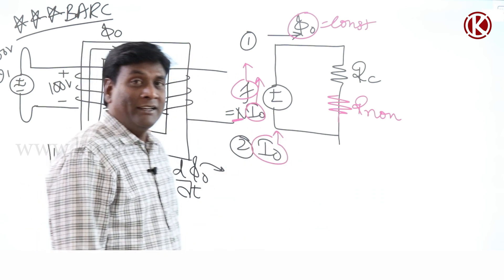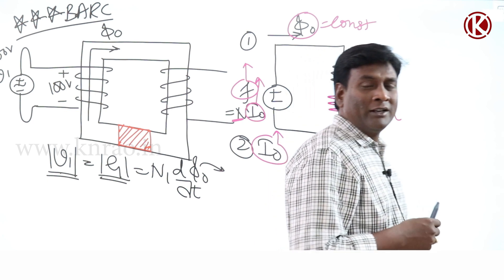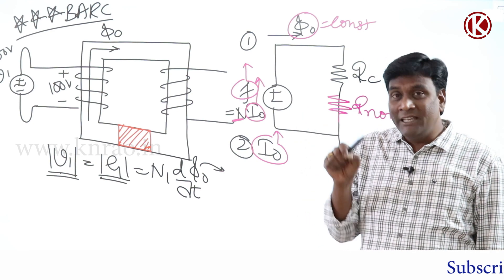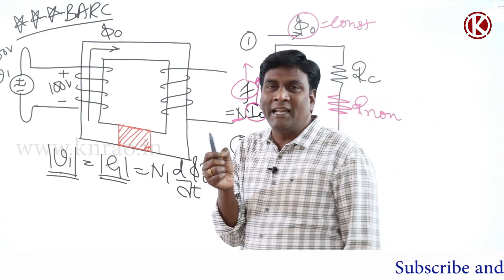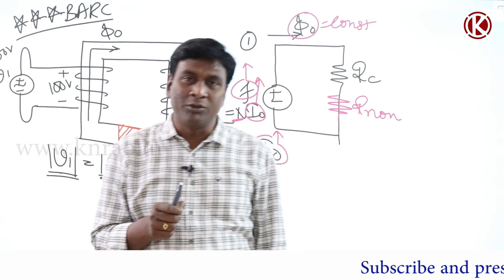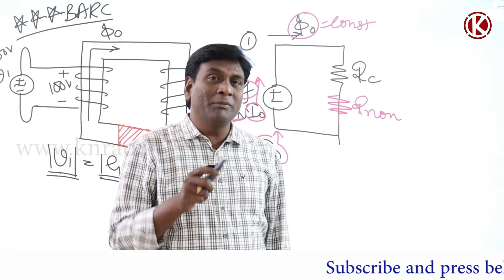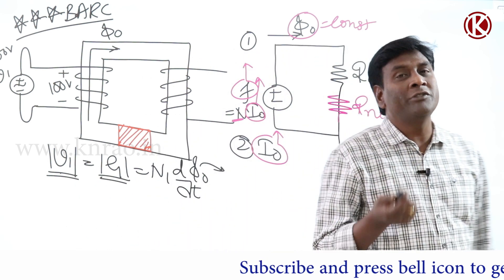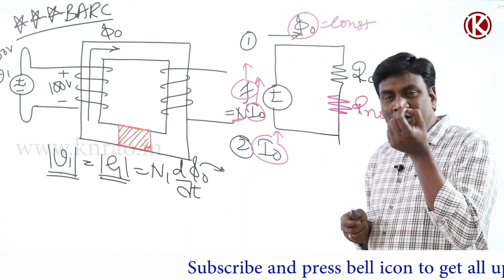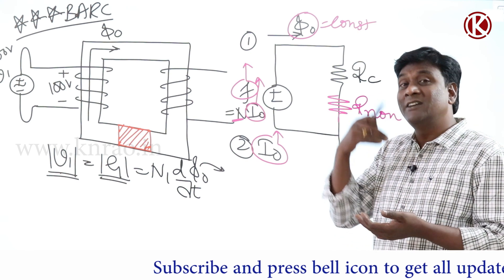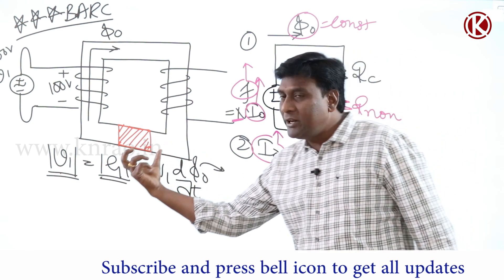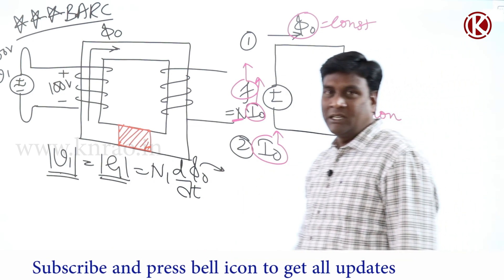To illustrate: if I give just a 2 mm air gap — which is 1 in 10,000 part of the total core — in order to set up the same amount of flux, to compensate for that small gap my no-load current was forced to increase by 25 percent. So if I give more air gap, the current to be injected will be tremendously high.